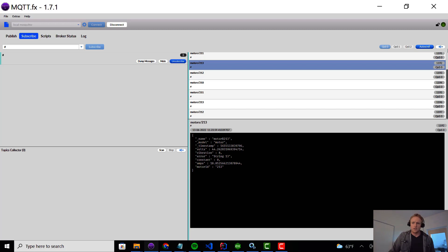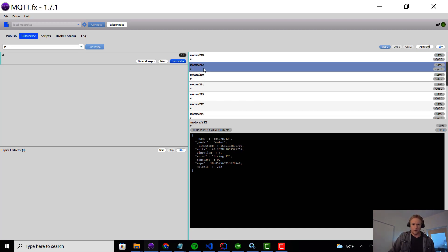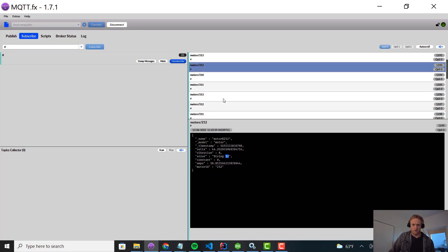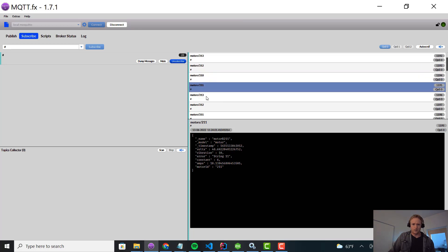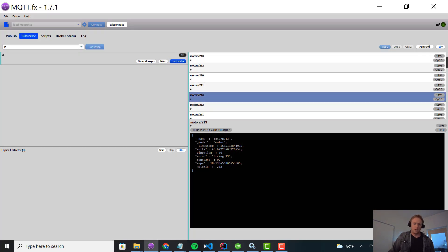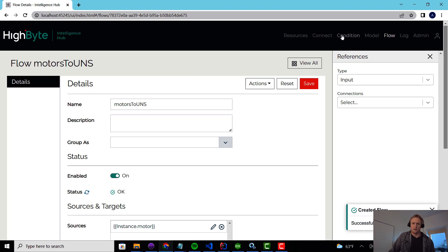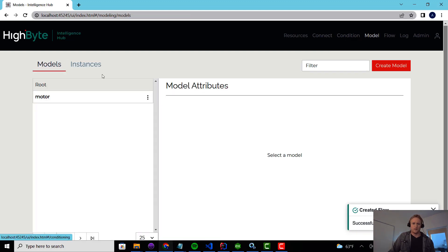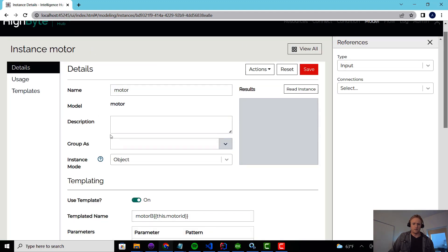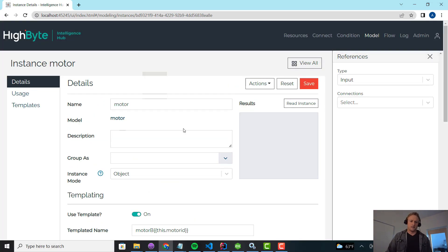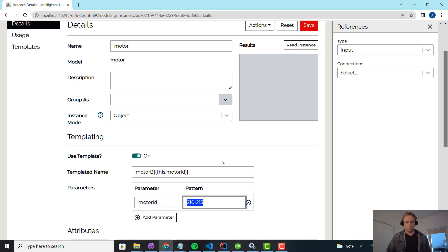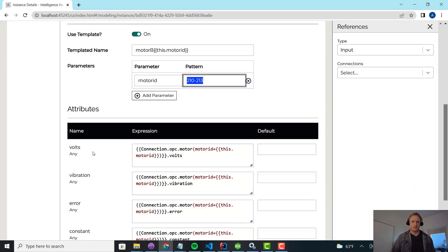If I did my work right — clear the buffer, turn on auto scroll — you'll see each one of the motors gets generated. Clicking on 212, that's 212. 210 is 210, 211, 213. Now if I added another motor, the only thing I'd need to do in HighByte is go into the instance definition and extend the range to 214. Through a single flow, single instance, single input — I'm passing data for all the motors. That's quite the optimization.